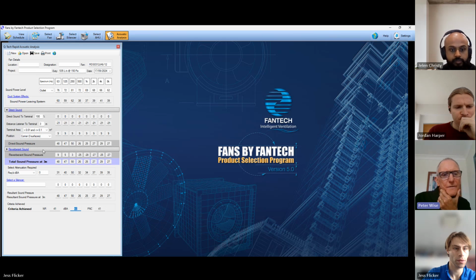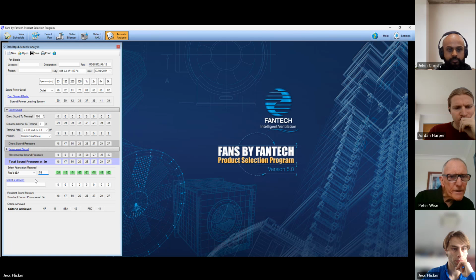So if you're selecting an attenuator, the line that says required dBA, you can put a number in there. You were talking about 55 dBA as the max, weren't you? Yeah, so if you put that in there, required dBA, select a silencer. So what that's saying is you don't need a silencer, I think. That's all it's telling you.